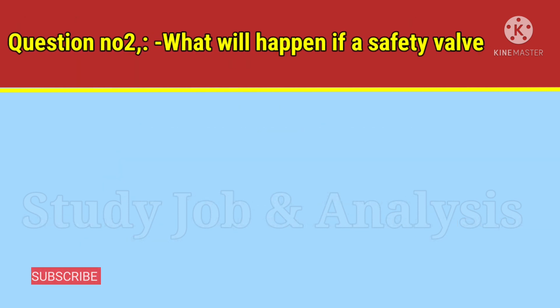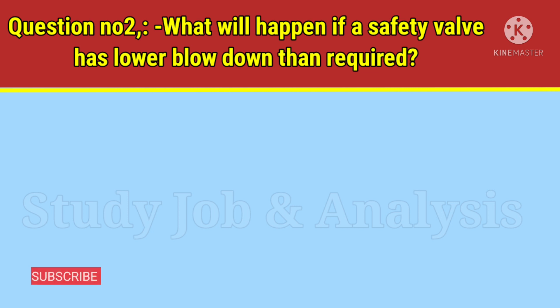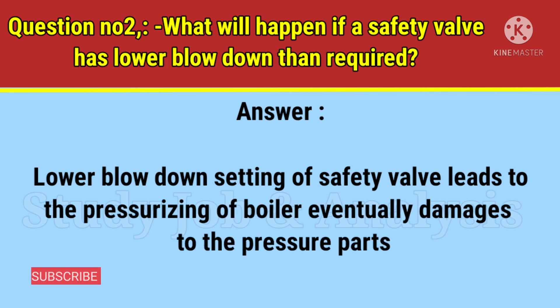Question number two: what will happen if a safety valve has lower blowdown than required? Answer: Low blowdown setting of a safety valve leads to over-pressurizing of the boiler, eventually causing damages to the pressure parts.